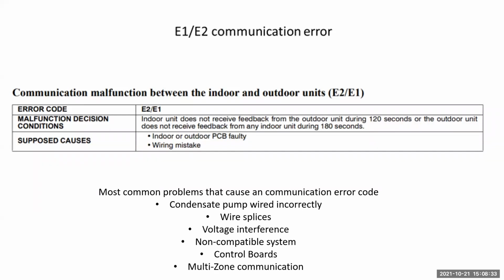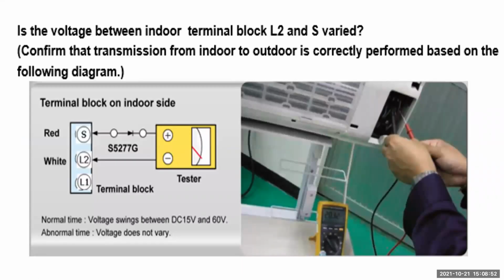You need to check your compatibility charts, make sure your indoor and outdoor units are compatible. On multi-zone systems, you need to make sure you have the correct A going to A, B going to B, C going to C. Then when you're checking for communication, you want to check DC voltage between L2 and S. The voltage should vary between 15 and 60 volts DC, and it's a good idea to check this at both the indoor and the outdoor units.